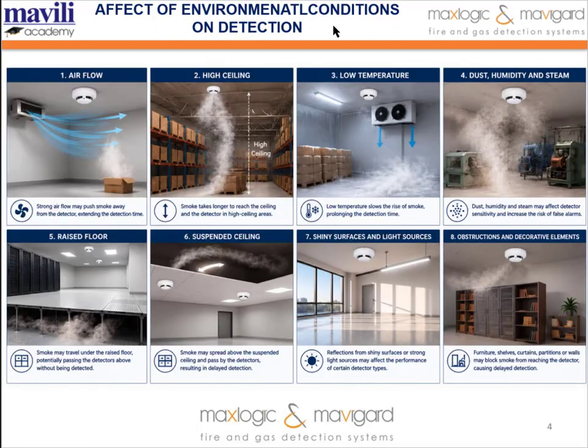Now, the effects of environmental conditions on detection. The first one is airflow, then high ceiling, low temperature, dust, humidity and steam, raised floor, suspended ceiling, shiny surfaces and light sources, and the last one is obstructions and decorative elements. Detection selection according to room type: first of all, for data centers, aspirating smoke detectors, point type smoke detectors, and raised floor detection can be used.